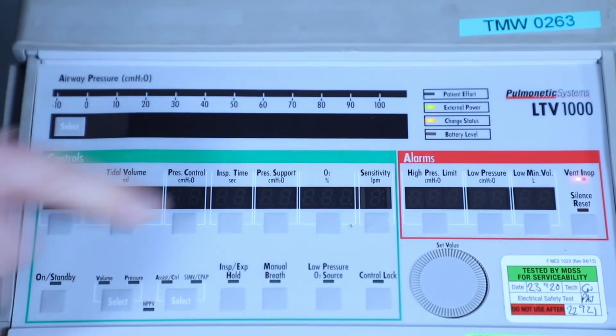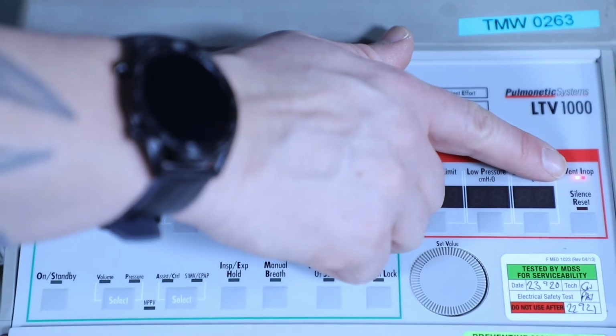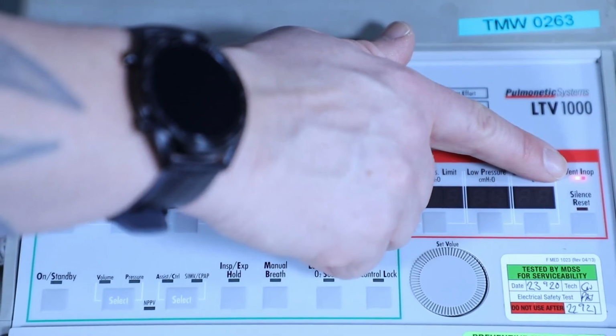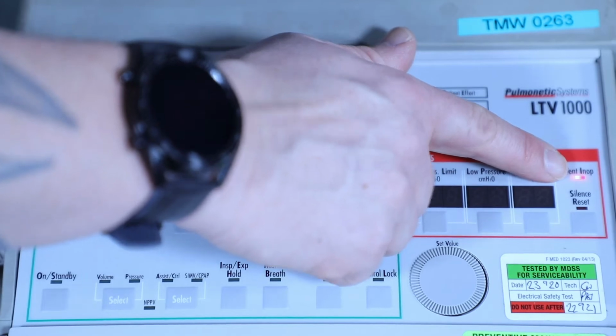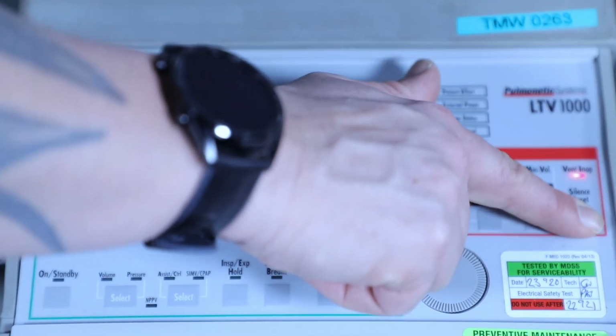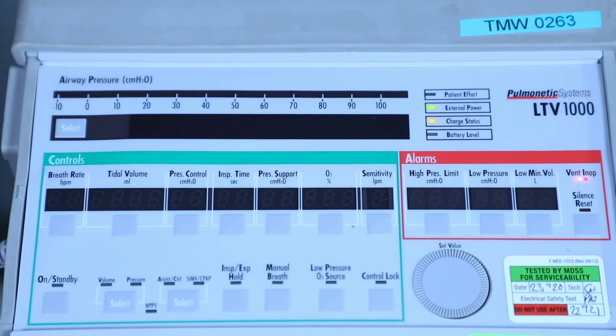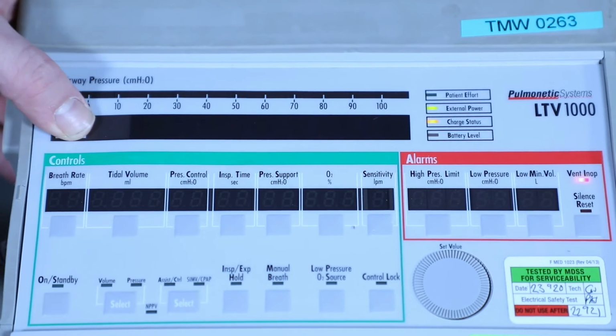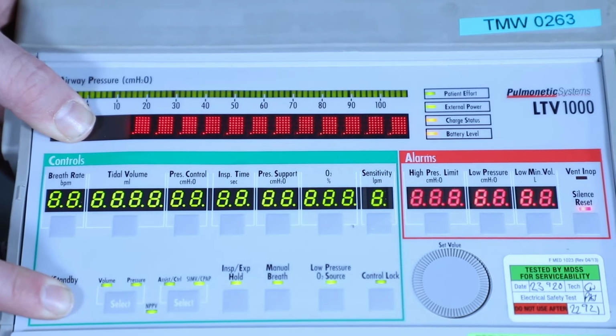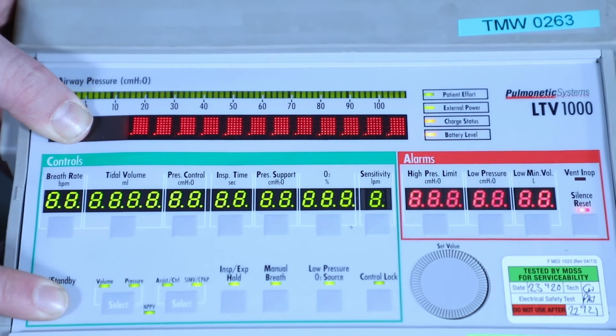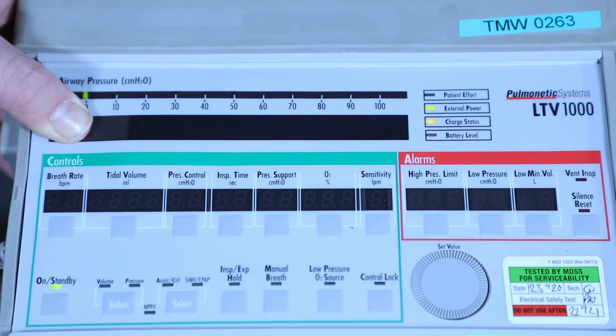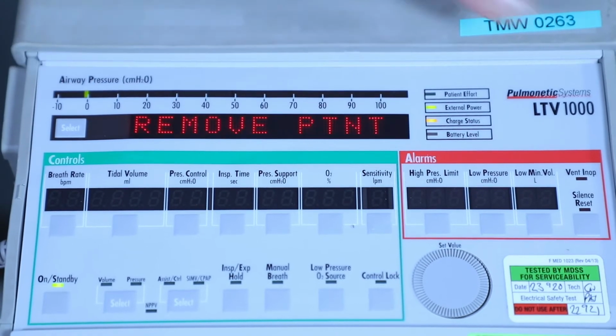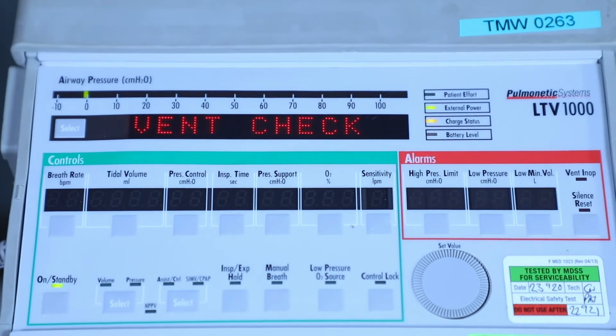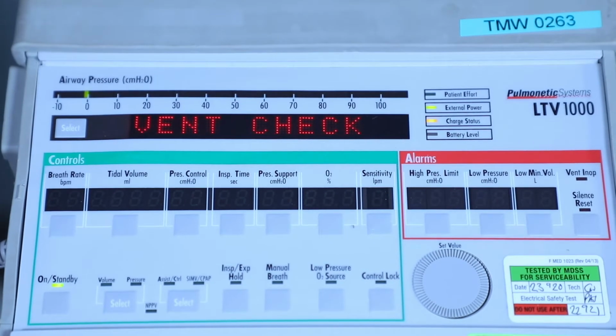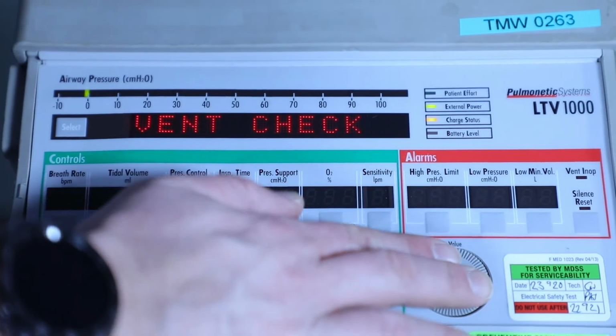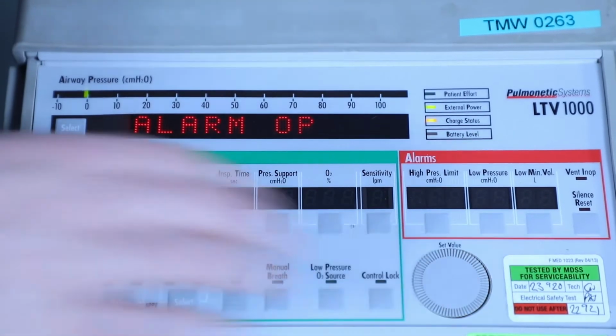The audible alarm will sound, the vent in-op alarm will illuminate. Allow the alarm to signal for 15 seconds and press silence. Switch the device back on in test mode, pressing and holding select, while simultaneously pressing the on-off button. Release and select when remove patient appears. The next menu we want to check is the alarm op.